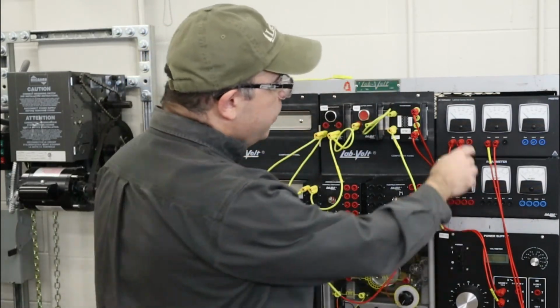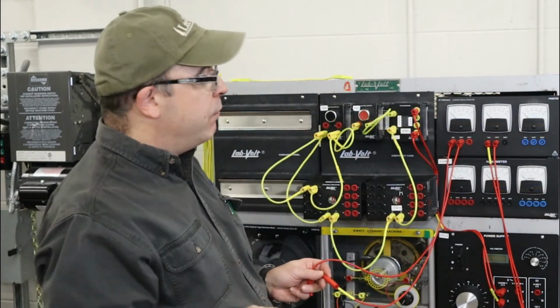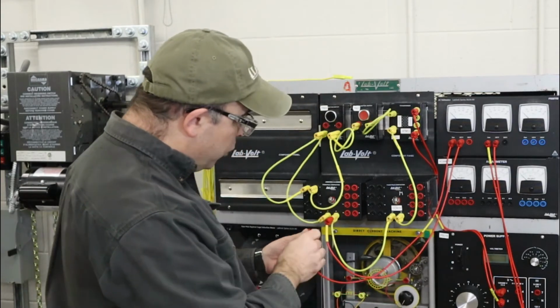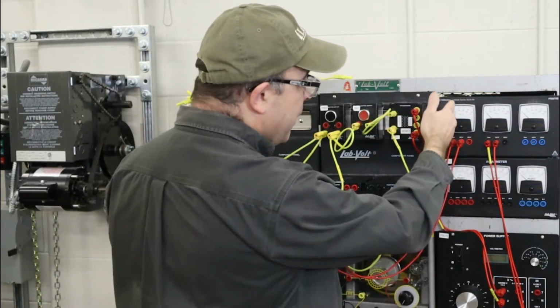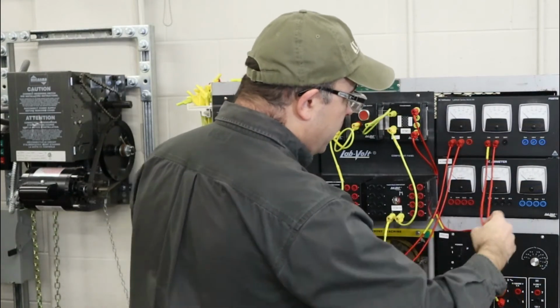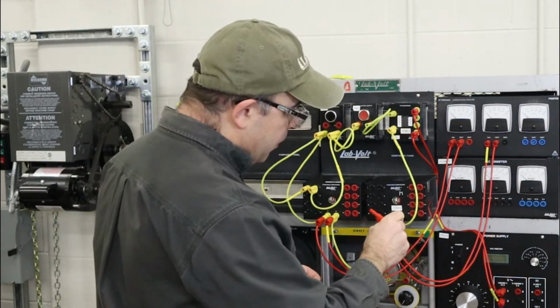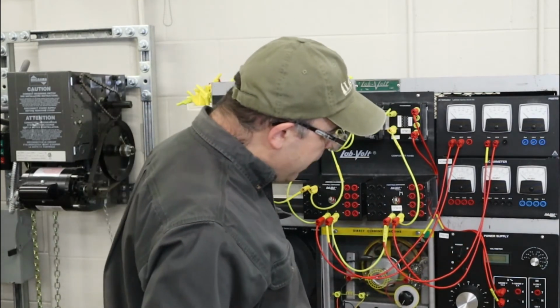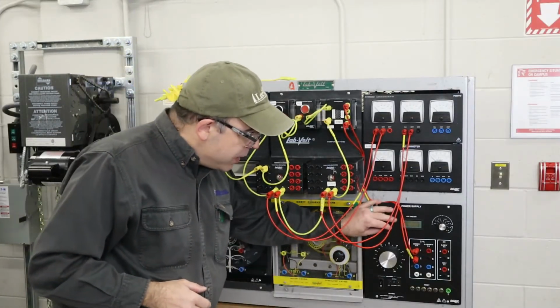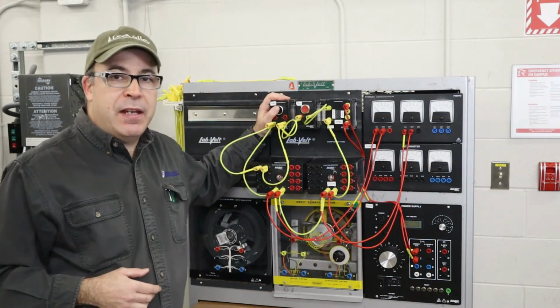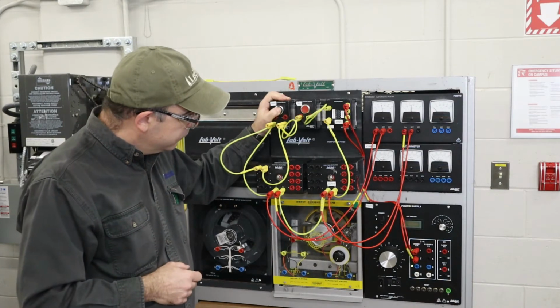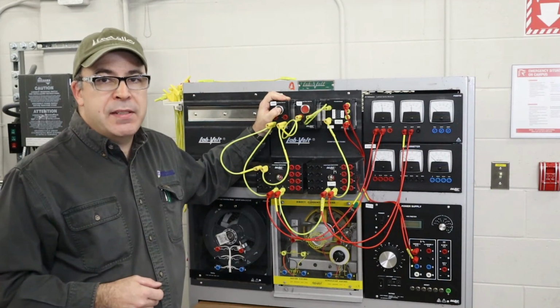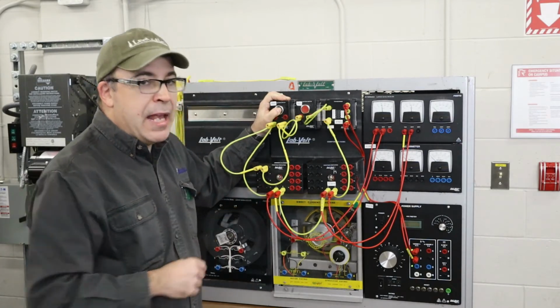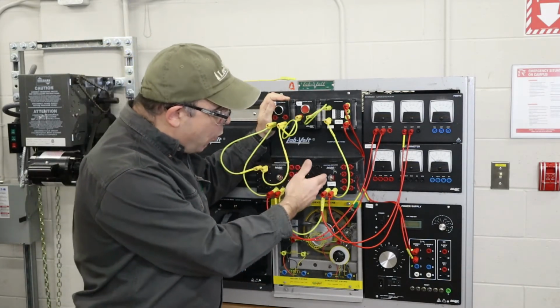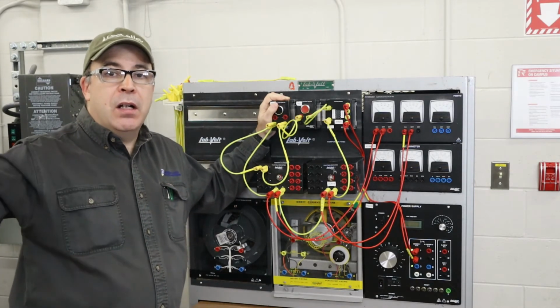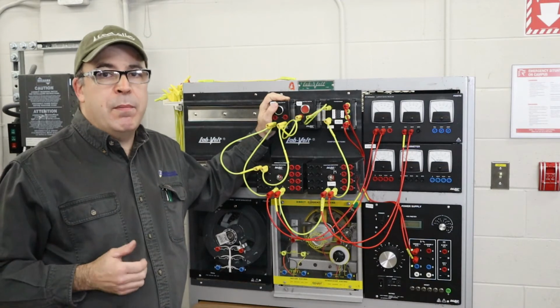I've got the voltmeter set on a 125 volt range, and we're going to take the voltage drop across the first relay coil for my first meter. The second meter is going to read the voltage drop across the second contactor coil. Now, all we have to do is energize our power supply and activate the circuit. Here goes. That humming or buzzing sound we hear is basically we do not have enough voltage going across both of these contactors as we saw on the whiteboard. We're actually coming up short of about 40 volts.